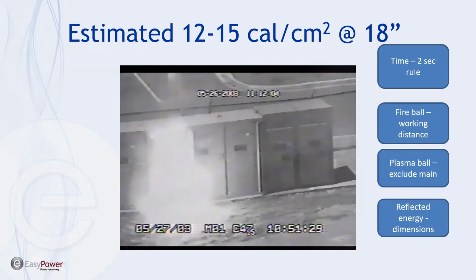But inside this fireball is the plasma ball, which probably measures anywhere from 1 inch to 3 inches in diameter. And it's what produced the heat and the pressure wave that they experienced. And it's interesting to point out this white vertical area up top. This is evidence of the reflected energy from the back, bottom, and sides of the cabinet, since they were looking at the only opening of a six-sided cube.